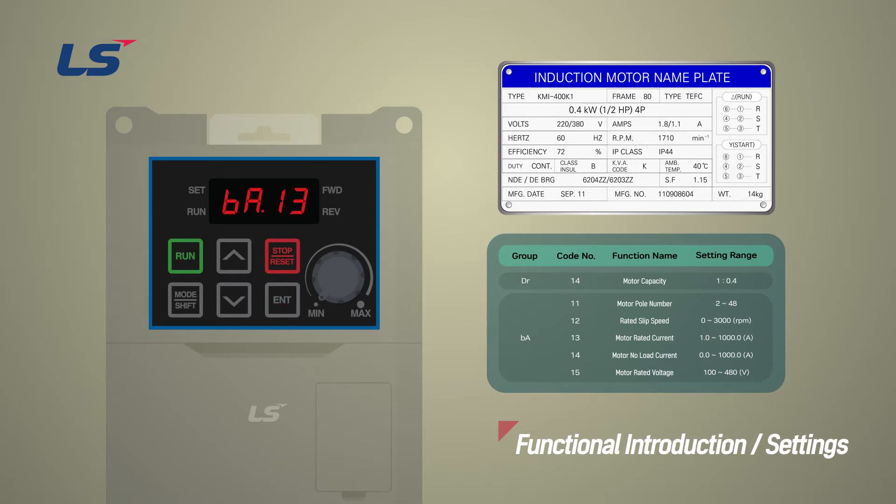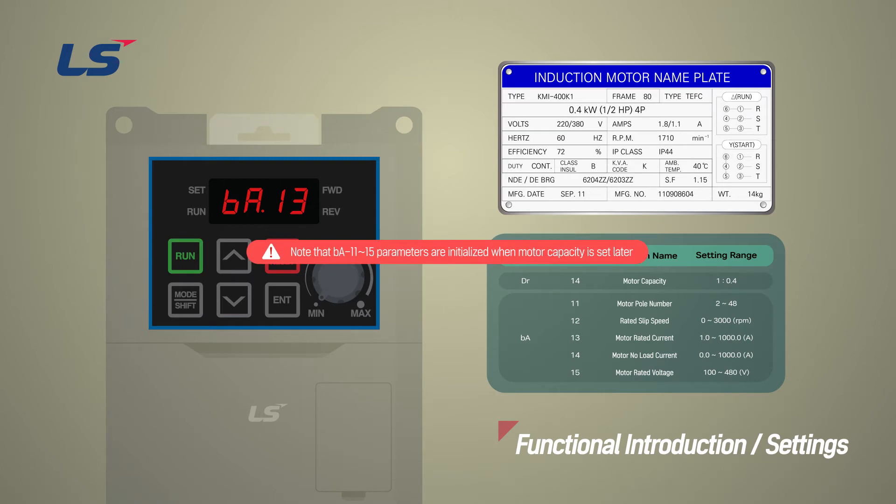Please note that if you change the order and set the motor capacity, DR14, later, the parameters BA11 to 15 will be initialized back to its default settings according to the changed capacity.